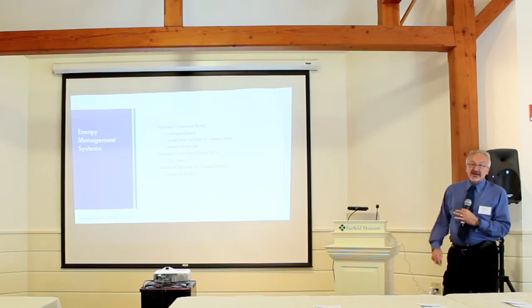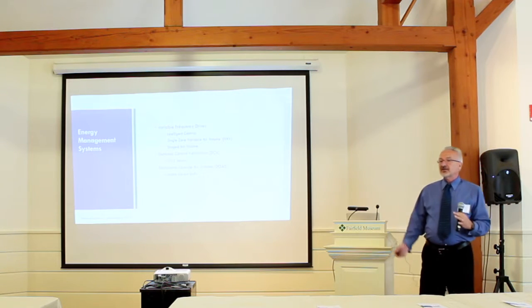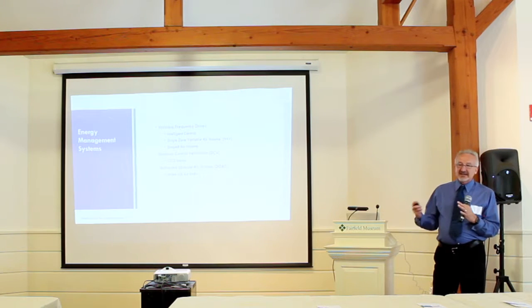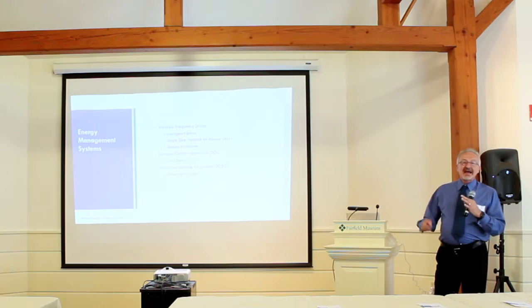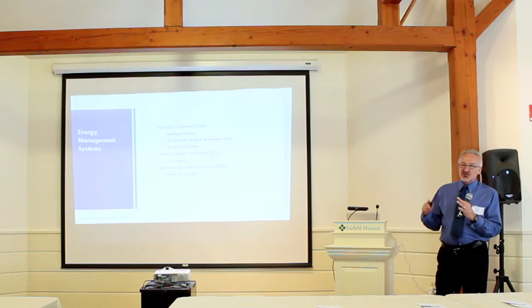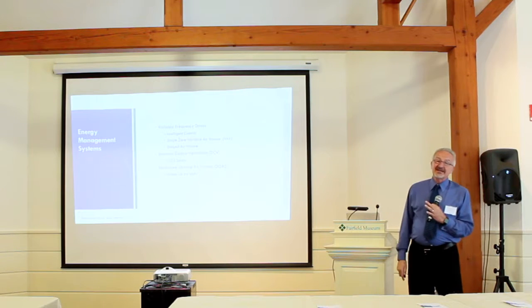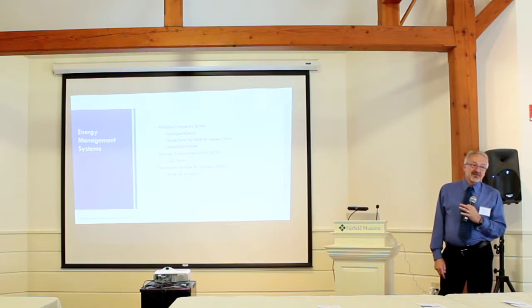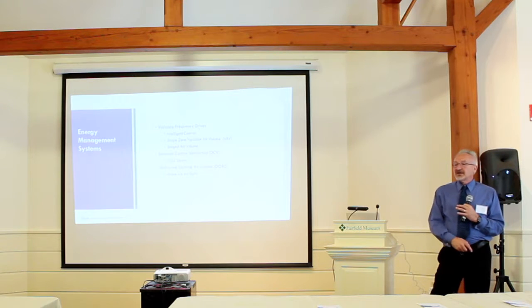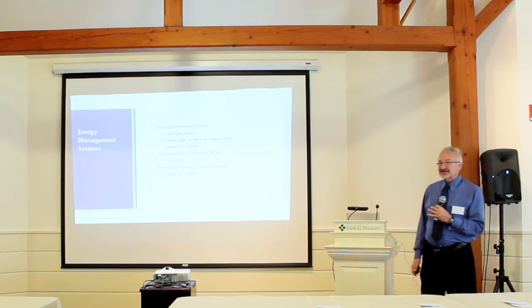And everybody says, I'm going to put variable frequency drives in, but you can put a variable frequency drive in and replace a conventional unit and not save any money. It's not the variable frequency drive that saves the energy, it's the control and operation and logic that you put in to operate that drive that makes the difference. So people come in, let's just put VFDs in everywhere, and they don't have a logic or a function behind it.